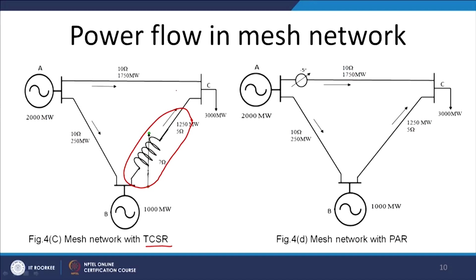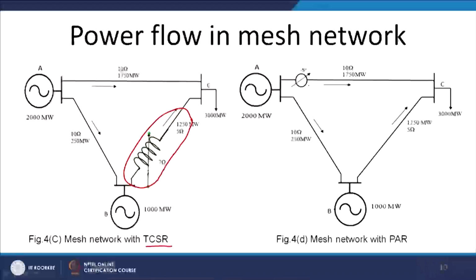Now what is the disadvantage of the previous one? The advantage of the previous one is that it has increased the power handling capability, so it may touch the thermal limit. Here, without inserting this device, we have inserted a device here and increased the extra impedance, and the same has been replicated to the line AB. The advantage here is that stability is more, but since impedance has been increased, the losses will be more. But another solution can be given by a phase angle regulator.